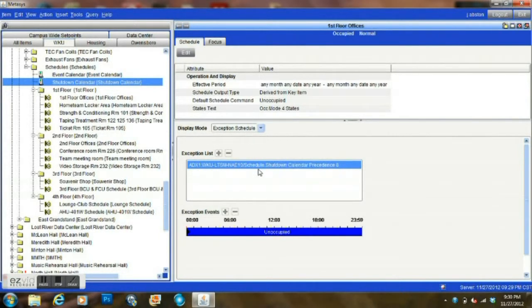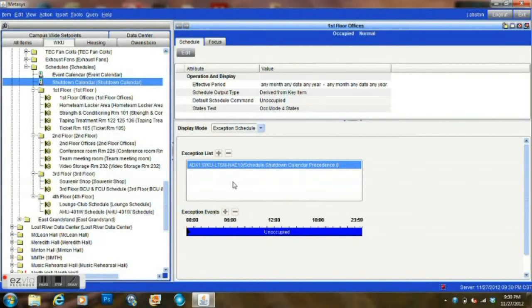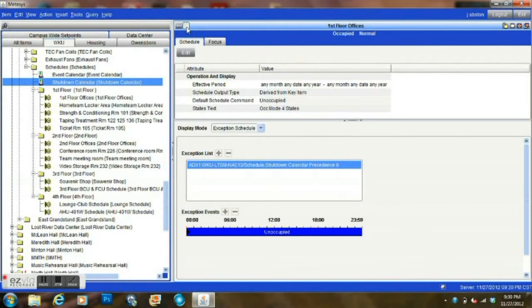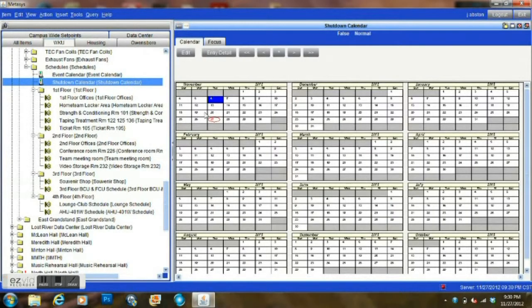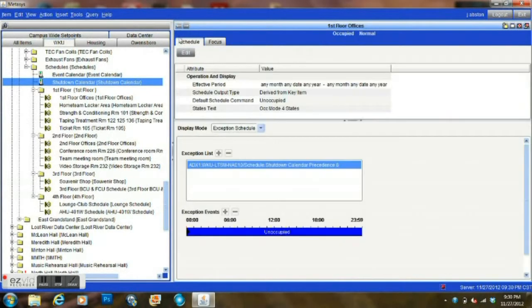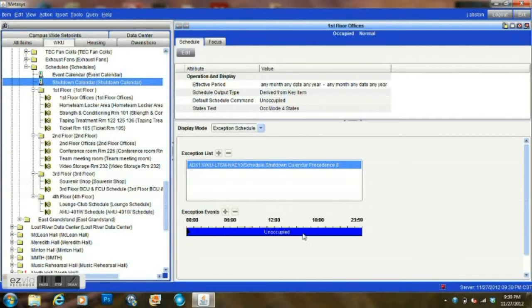The calendar works just like an exception schedule, but instead of setting a particular day or month or any particular date, it will simply cause this schedule to look for the dates which are highlighted in a calendar. Now then, once that schedule is tied to a particular calendar, you will then use this down here to set your time.